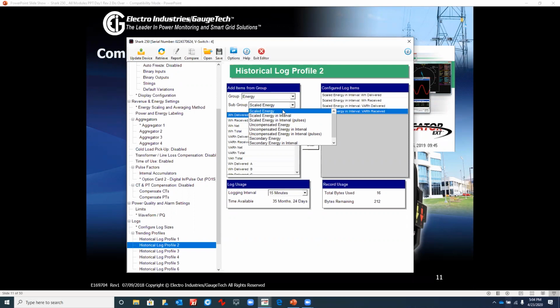So scaled energy is basically the registers that are on the display of the meter that are brought into a log file. So every time you read the meter, you take a snapshot of a reading, it comes in. It basically is a snapshot of the reading on the display, stores that into a location at a particular time. The next time you read it again, let's say you read the meter at 11 o'clock, it would post a reading for that. So this is a good way of actually capturing readings in the meter. That, let's say you wanted a reading last month at 11 o'clock at night or some event, you can go back and retrieve the historical log set for scaled energy and bring that information back.